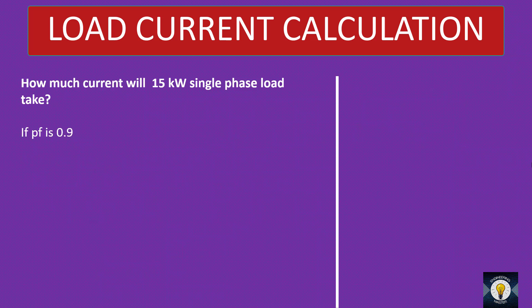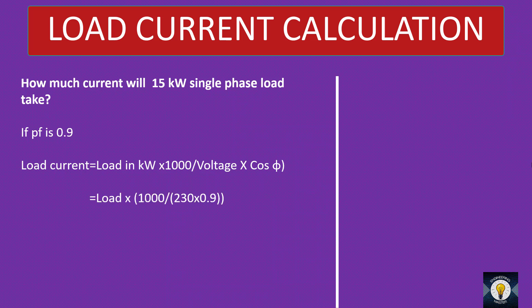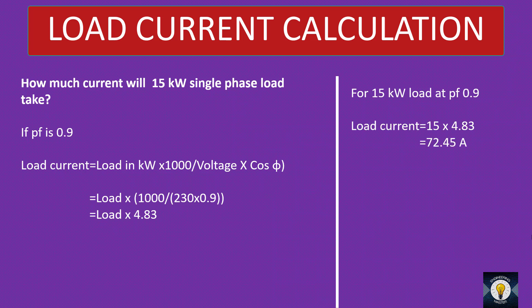If the power factor is 0.9, the equation becomes load current equals load in kW into 1000 divided by voltage into cos φ — that is load into 1000 divided by 230 into 0.9 — giving load into 4.83. For 15 kW at power factor 0.9, the load current is 15 into 4.83, which is 72.45 A. For 15 kW at 0.8 power factor, the load current is 15 into 5.43, that is 81.45 A.